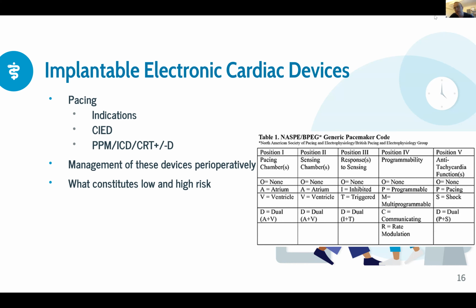you then need to think about the nature of the surgery. Is it emergent versus elective? If it's elective, it can wait. You get the physiologist to have a look at the device and to set it appropriately. If it's emergency, then it's on you and the surgeon to decide what's the best way to manage it, and it might be discussing with them where you put the diathermy pad. Can you do it without monopolar? And you just need to have a way of balancing all those risks. So that's permanent pacemakers. The second type of device is going to be ICDs.